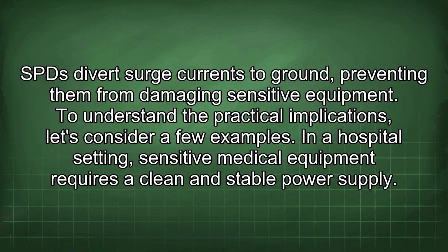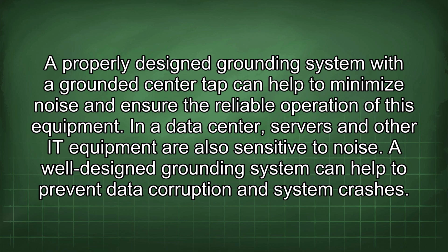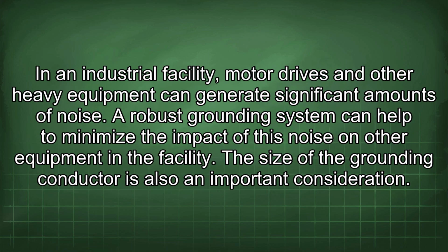To understand the practical implications, let's consider a few examples. In a hospital setting, sensitive medical equipment requires a clean and stable power supply. A properly designed grounding system with a grounded center tap can help to minimize noise and ensure the reliable operation of this equipment. In a data center, servers and other IT equipment are also sensitive to noise. A well-designed grounding system can help to prevent data corruption and system crashes. In an industrial facility, motor drives and other heavy equipment can generate significant amounts of noise. A robust grounding system can help to minimize the impact of this noise on other equipment in the facility.